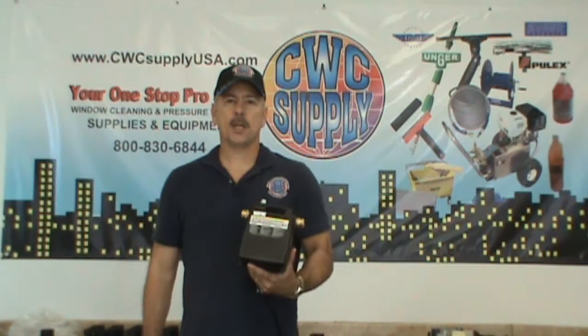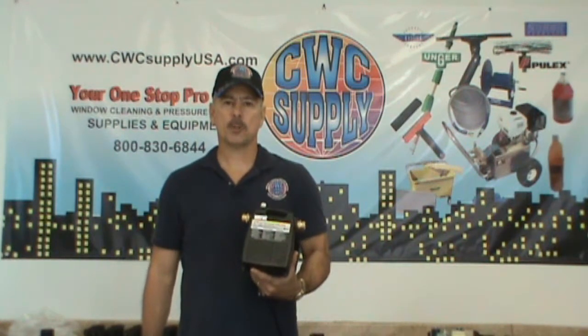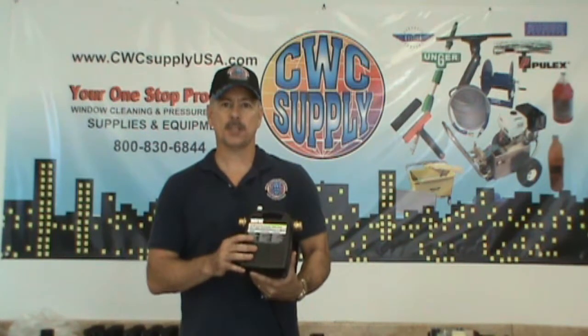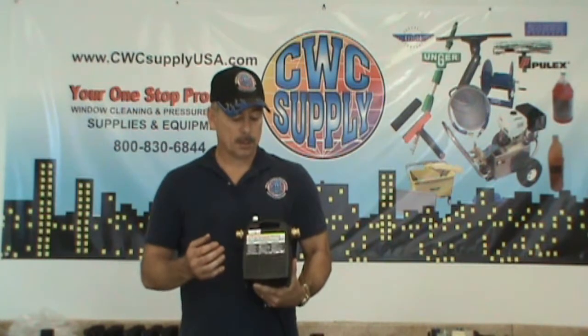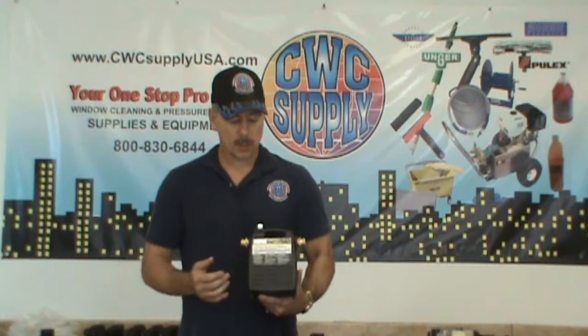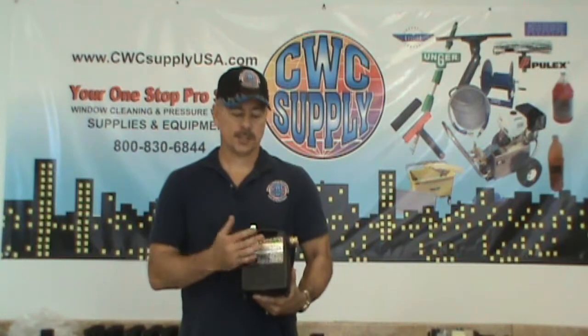Hi, this is Tom with CWC Supply and I'd like to introduce you to the Wayne PC4 half horsepower booster pump. This pump is a half horsepower and gives you the ability to increase your pressure coming out of your RODI system from 50 up to 250 PSI. It has in and out garden hose connections and a heavy duty cast iron housing. All you have to do is inline this between your water source and your purification system.